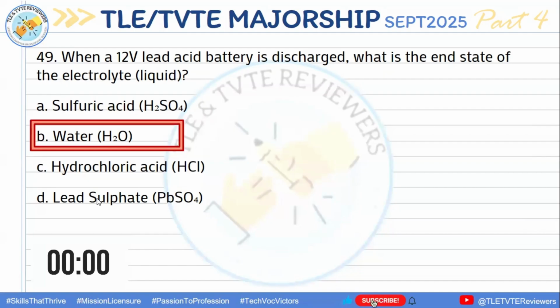Answer letter B, water or H2O. During discharge, the sulfuric acid in the electrolyte reacts with the lead plates and forms lead sulfate on the plates. This reaction causes the sulfuric acid concentration in the electrolyte to decrease, effectively diluting the electrolyte into mostly water. So, as the battery discharges, the electrolyte becomes more like water.